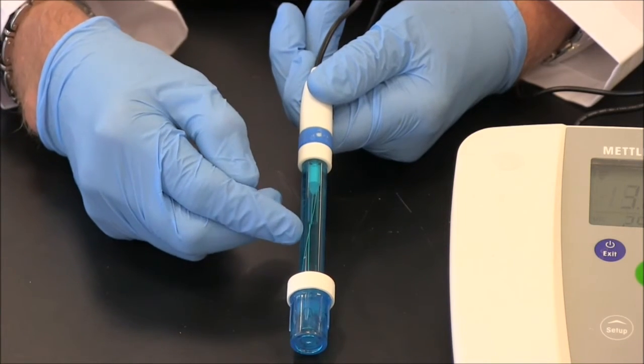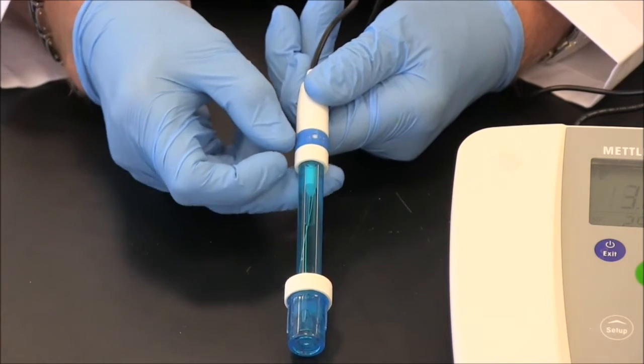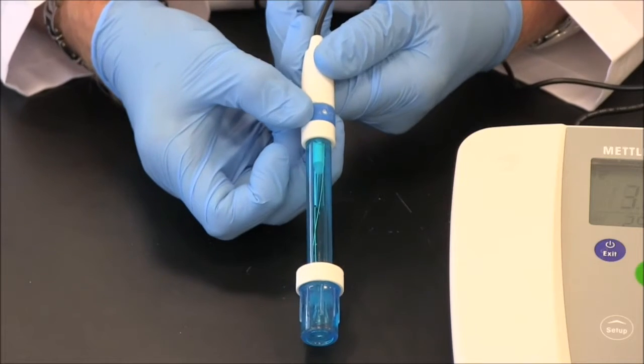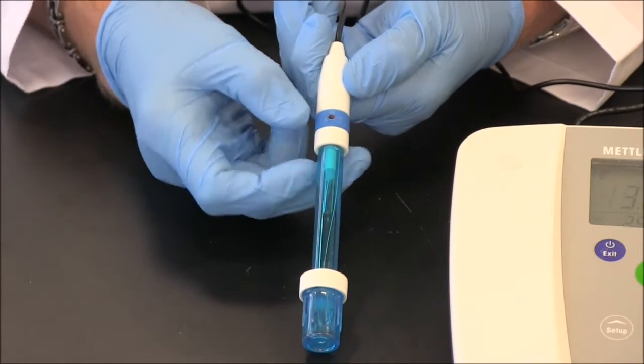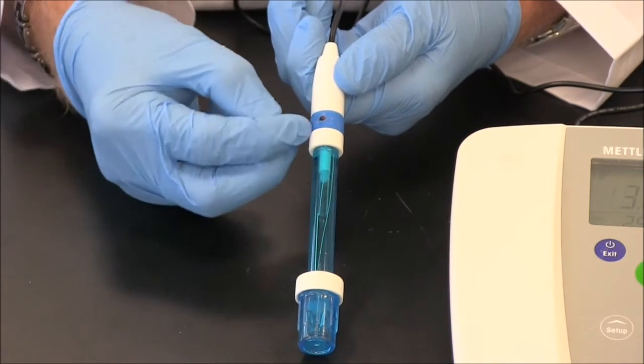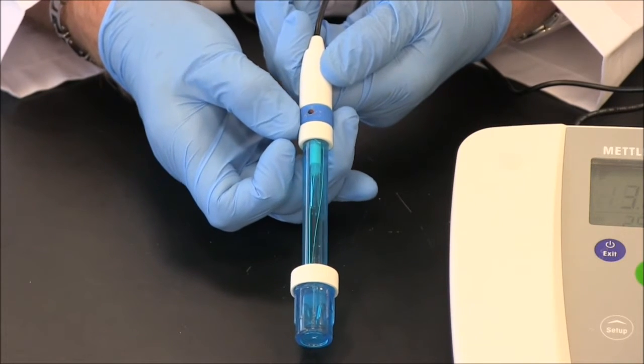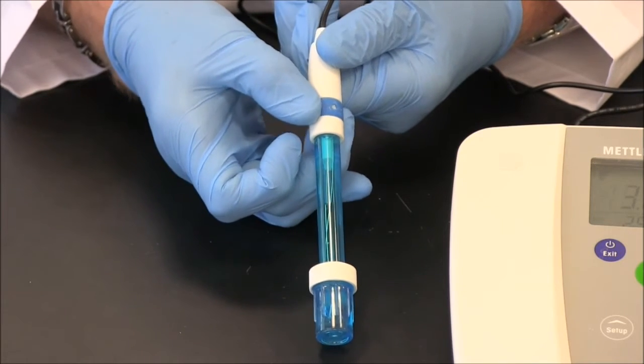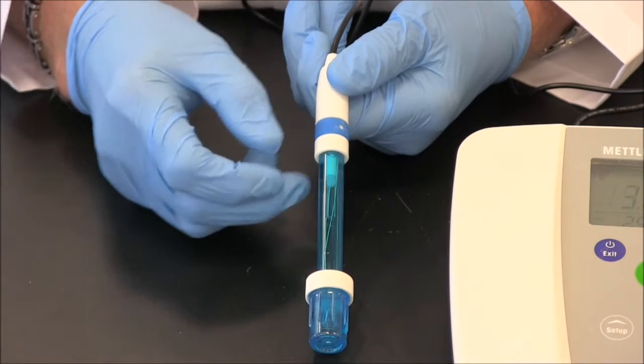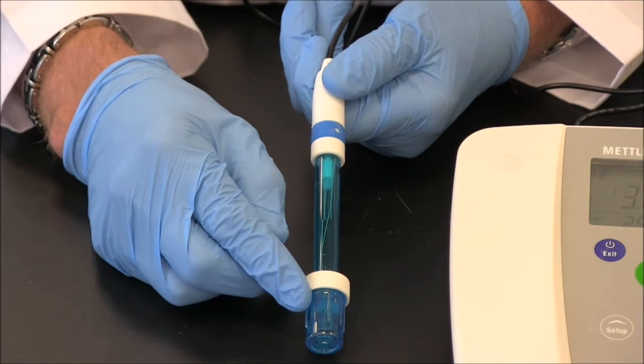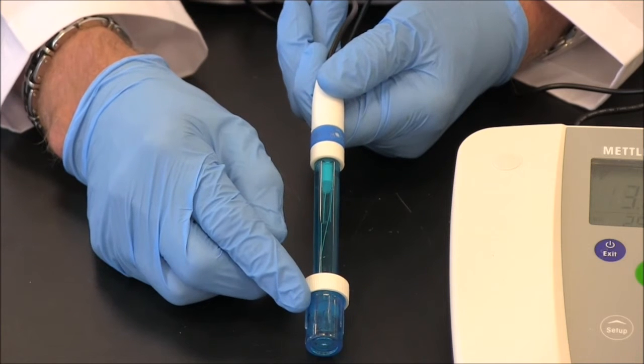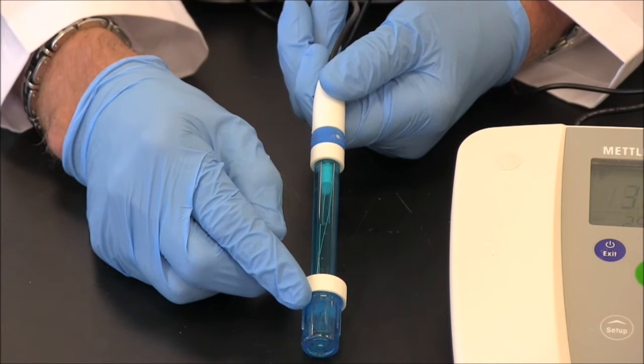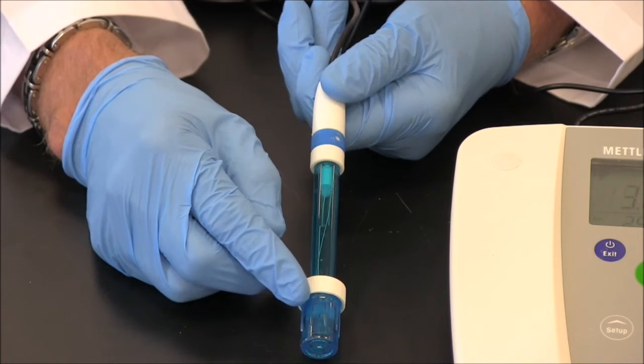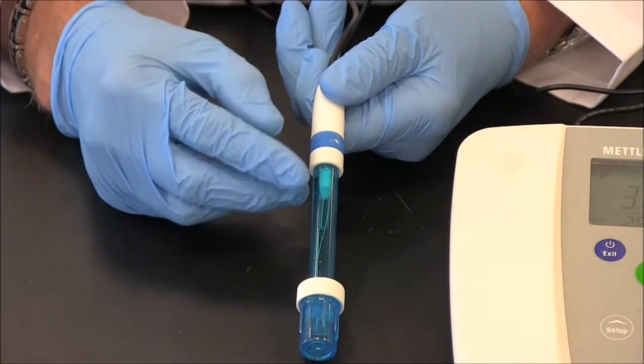You should always check your probe ahead of time to make sure that it's not dried out. If it has, there's usually an opening at the top, and by twisting the collar you can top it up with the reference solution. Make sure it's closed though when you're reading so that it doesn't dry out. The other important part is at the bottom of the pH electrode, which is where the pH-sensitive glass membrane is. The hydrogen ions move through the pores to create a potential difference that can be detected by the meter.